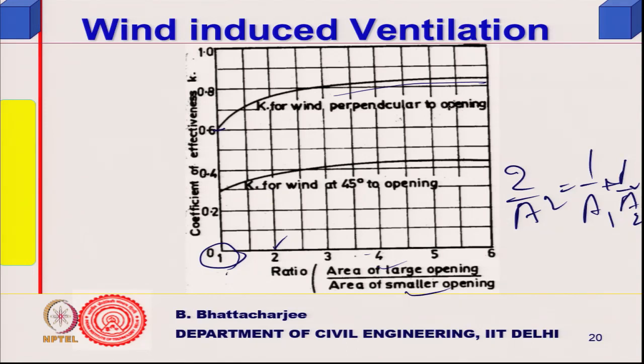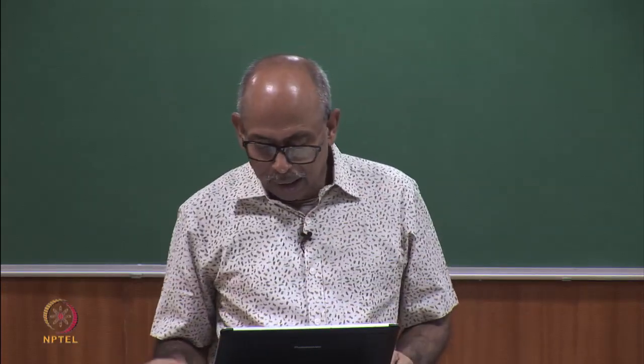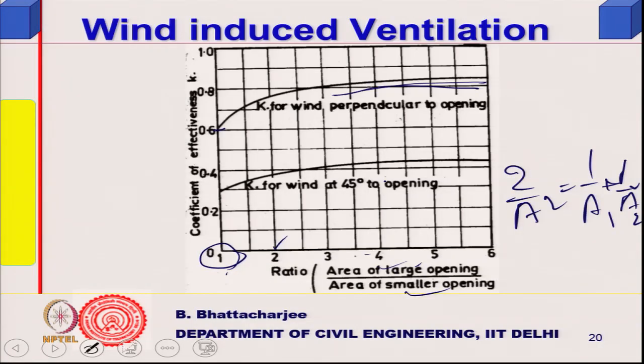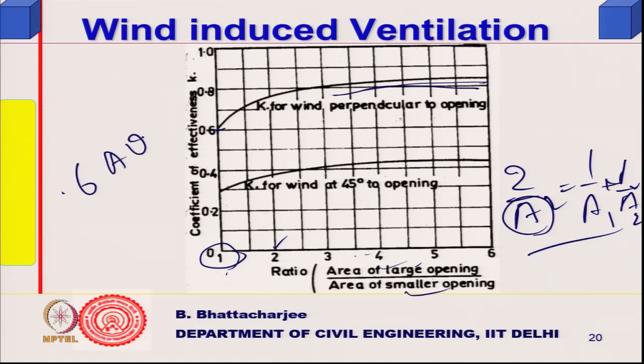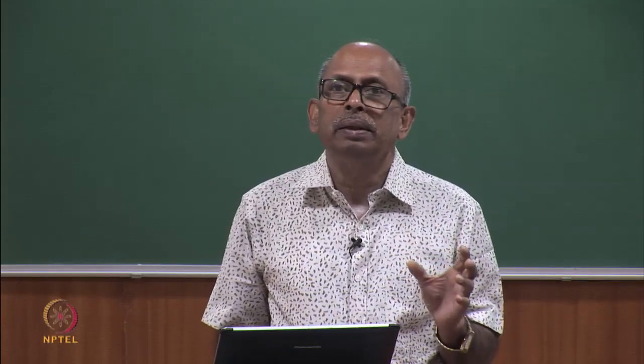When you take the smaller opening area with these coefficients, you need not worry about the coefficient separately. Calculate an equivalent area and use 0.6 times equivalent area times velocity. SP 41 also provides a curve for the 45-degree case where the value is 0.3. This gives you the flow due to wind as the driving force.